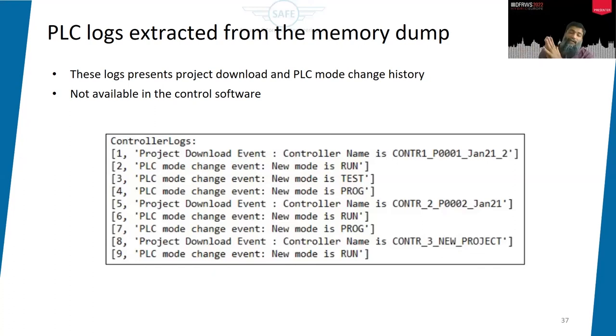We were also able to extract some logs that were not even available in the control software. These logs tell us that the PLC mode was changed to run, test, and program mode. If somebody changed the mode to program mode, something was definitely going on — unless it matches the expected user activity. In larger environments, SOPs are in place whenever a program change occurs, so if the logs match or don't match those SOPs, it reveals whether there is an anomaly.